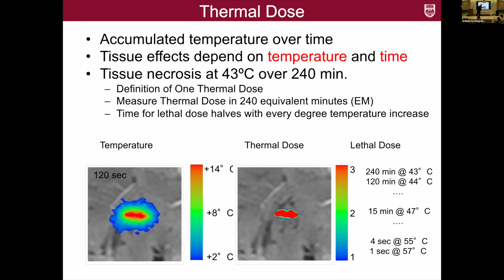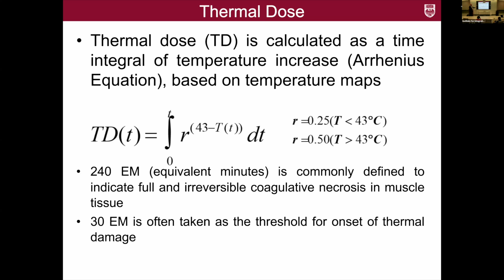The thermal dose is calculated according to the Arrhenius equation, and we can then calculate these temperature maps. These are the 240 equivalent minutes, which is commonly defined to indicate a full and irreversible coagulative necrosis in muscle tissue. The 30 EM is often taken as a threshold for the onset of thermal damage, so we have to be careful. We have to spare the other organs around it, so we should not exceed it. You can see that here. So 0 to 30, no thermal damage. If we go above, somewhere in between and 240, we have possible thermal damage. And as soon as we reach the 240 equivalent minutes, we have an irreversible coagulative necrosis, which is what we of course want to achieve in a tumor to ablate it.